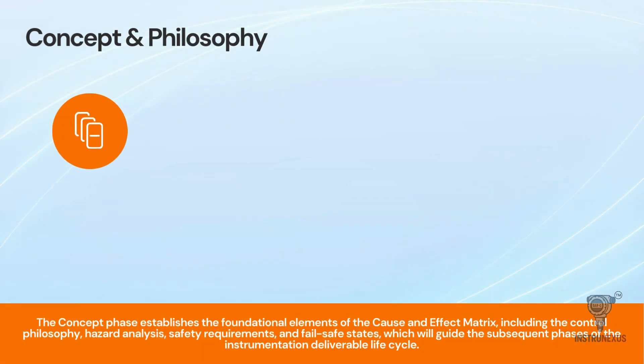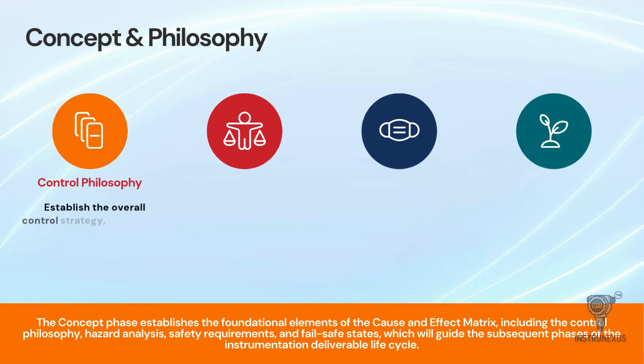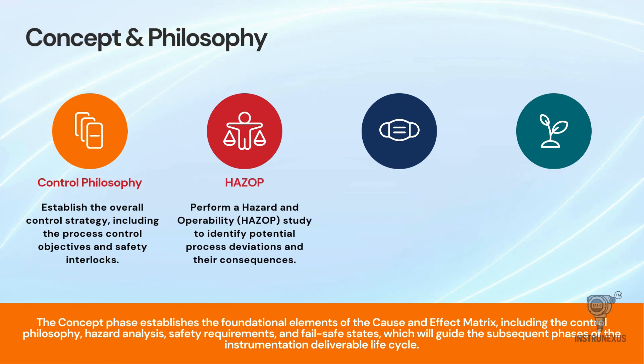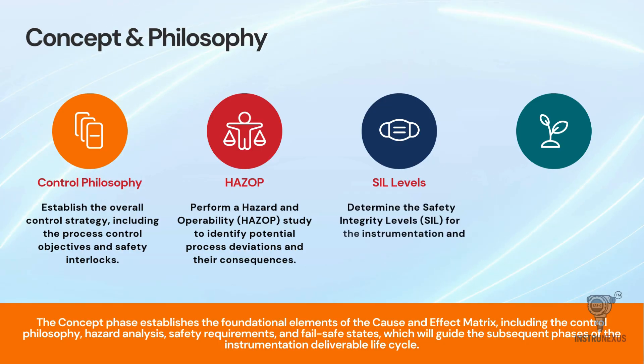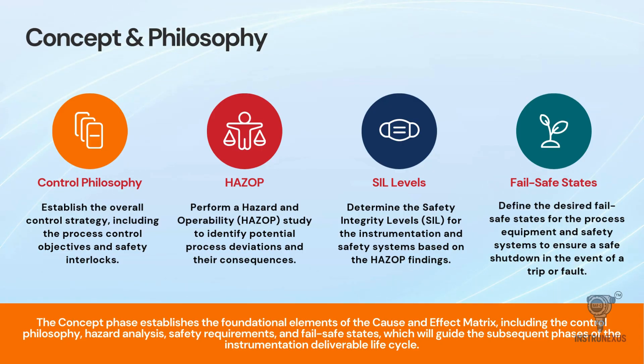Everything starts with the concept phase. Before we draw a single grid line, we must establish the control philosophy. This sets the strategy for our process control objectives and safety interlocks. During this phase, engineers perform a HAZOP — hazard and operability study — to identify what could go wrong in the process. Based on that study, we determine the safety integrity levels, or SIL, required for the system. Crucially, we also define the fail-safe states. If the power goes out or a wire is cut, should the valve close or open? Defining these states early ensures that the plant defaults to a safe shutdown condition in the event of a fault.